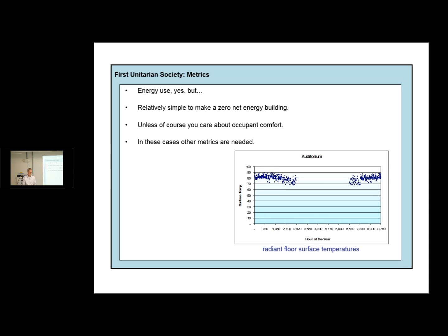Another thing we looked at was the difference in performance between using an energy recovery ventilator, a mechanical device, and using an earth duct, a more passive device. The idea of an earth duct, if you haven't run across one, is you've got a bunch of tubes buried in the ground, and you're drawing your building's outdoor air down through the ground and then up into the building. The hope is that in the wintertime you pick up a bit of energy because the ground is warmer than the air, if you go deep enough, below the frost line. In summertime, you draw that air in and pre-cool it. So it's a passive device.